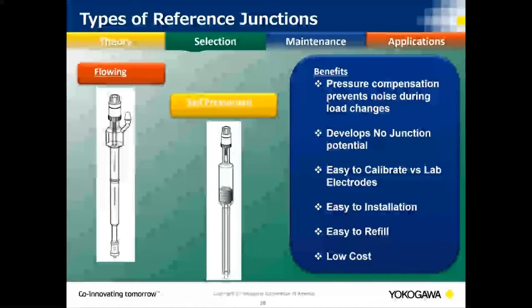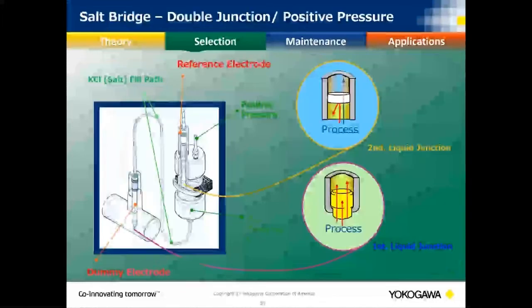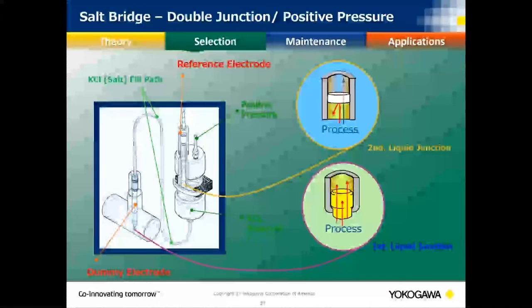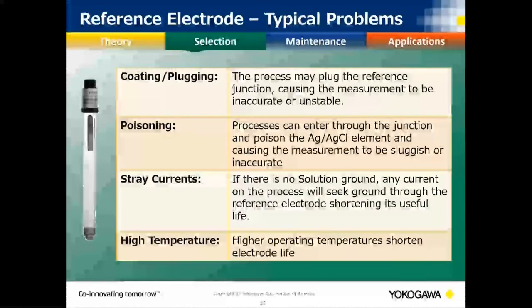In ultra-pure water applications, flowing-type junctions are common. Because the process is essentially pure water with no ions, we need to maintain continuity, so we use an open junction that allows a complete circuit between the ORP electrode and the reference. Any problems with your pH reference — coating, plugging, process poisoning — you will also have with your ORP reference.